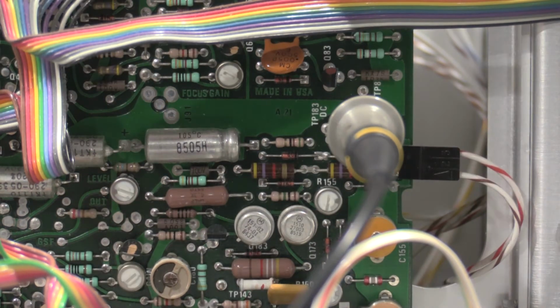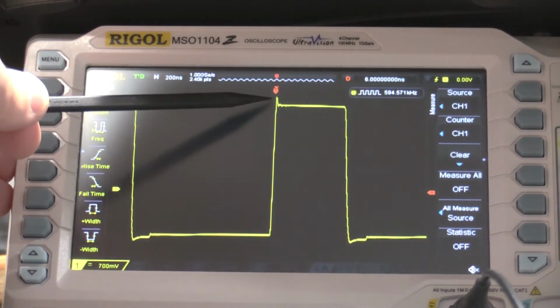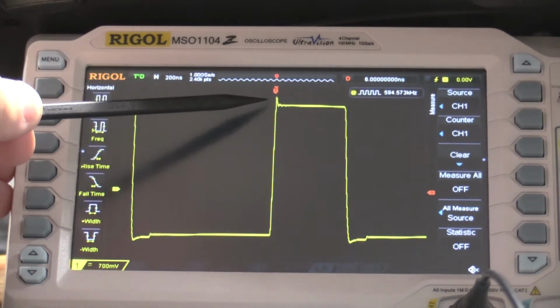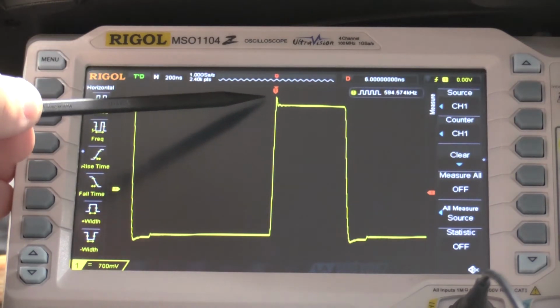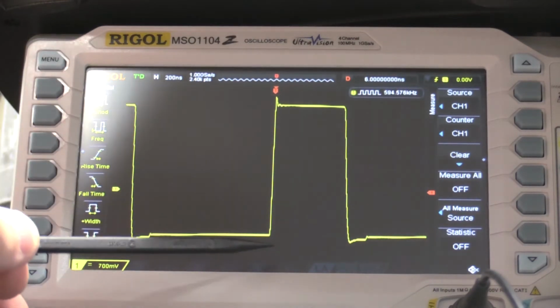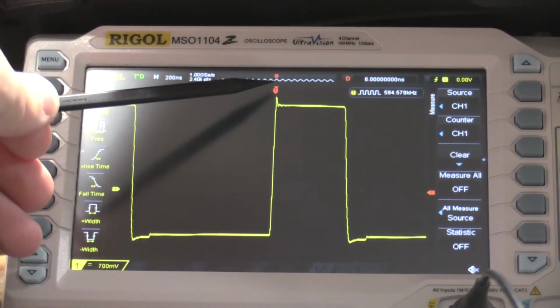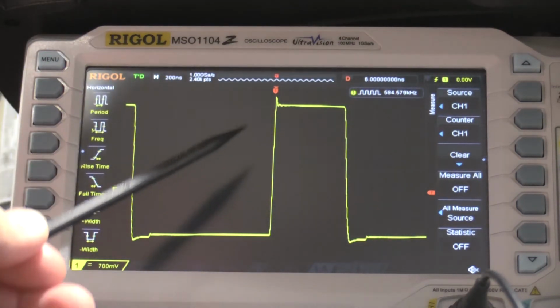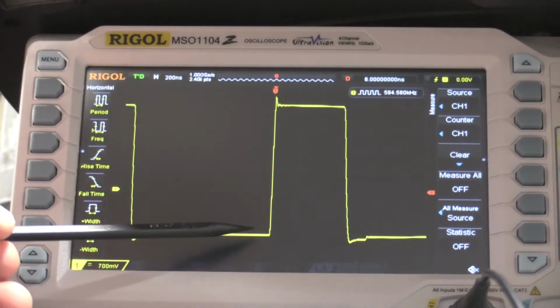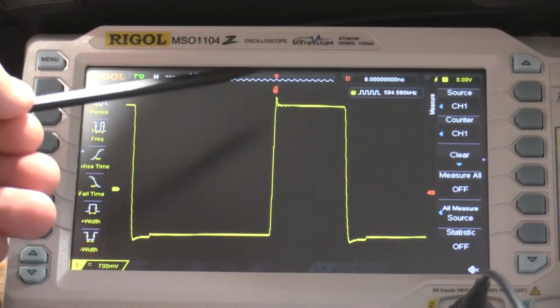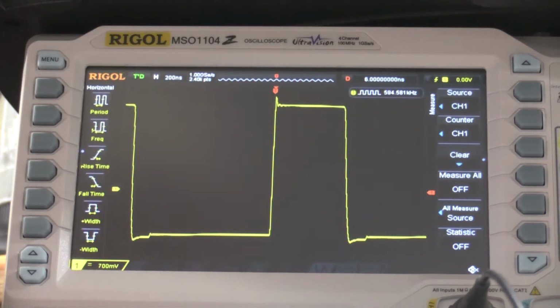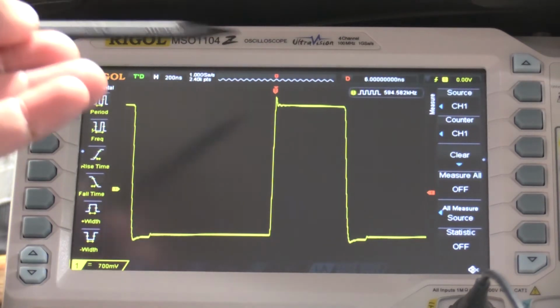So this looks okay, but it is out of adjustment. So I'll move over to the scope and we'll take a look at that. So what I'm looking at is this corner right here. This is a little peaked up, so I need to tamp this down a little bit. So we want this to be a nice straight edge as fast as possible, so we don't want it to roll up, because if it's rolling up, that's too slow. So you want it to bounce up, but then you want these aberrations at the very front corner to be less. So I'll focus in on the amp while I'm doing the adjustment, and then I will focus back in on the scope.